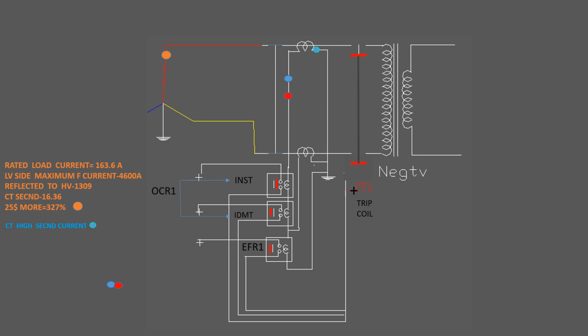Next, this IDMT relay. I will not show the same characteristics, but it is permitting overload. So the program is given for that current: if this overload clears within a certain period, that means permitting the transformer 200% for 5 minutes and 150% load for 15 minutes. If it is less than this time, then the CB will not trip, it will continue. Now I will show the earth fault relay.